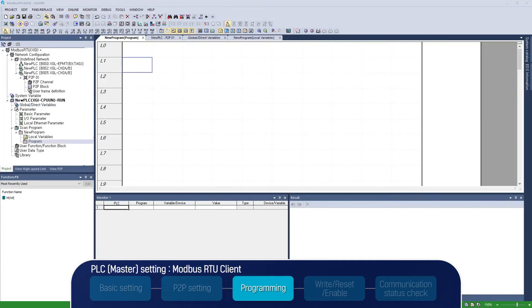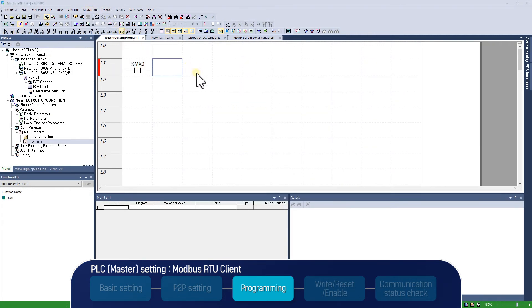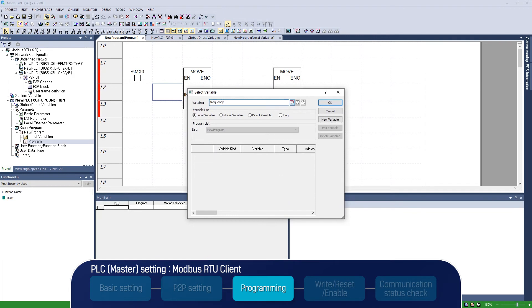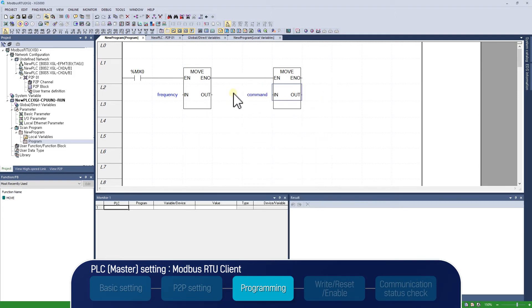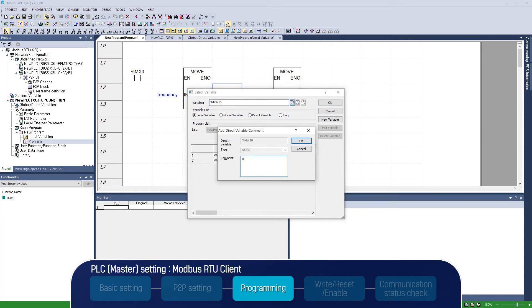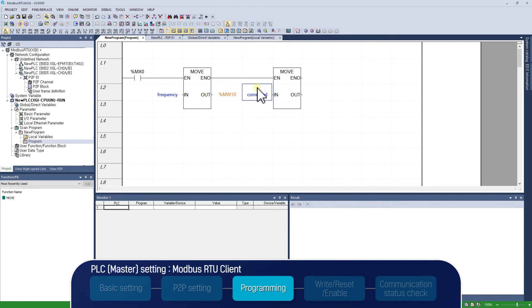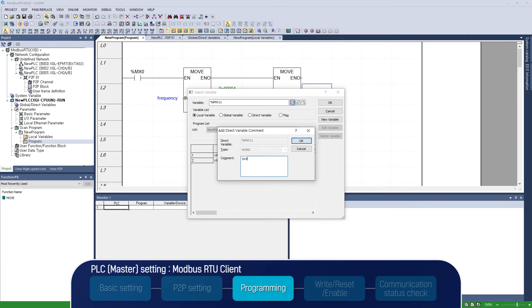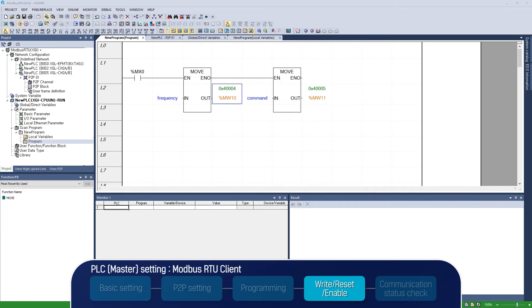After completing P2P setting, we will make a program to see how to write the data to the drive. The following program is to move data for reference frequency and run command to MW10 and MW11, assigned to the address of the drive communication when MX0 bit turns on. PLC address MW10 is assigned to 0x4 00004 of reference frequency, and MW11 is to 0x4 00005 of run command. After completing the PLC program, download it to the PLC.